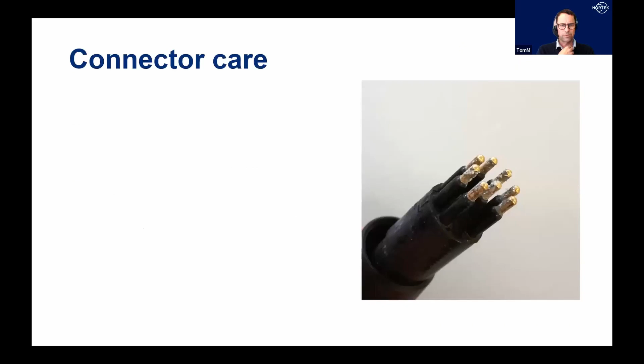Inspect for damage and corrosion. If for some reason you see corrosion on the dummy plugs, you'll need to change the bulkhead of the instrument, because then the dummy plug and connector are damaged, and eventually the instrument will leak. Whenever you see corrosion on a dummy plug, like in the picture here, you need to send the instrument in to replace the underwater bulkhead.